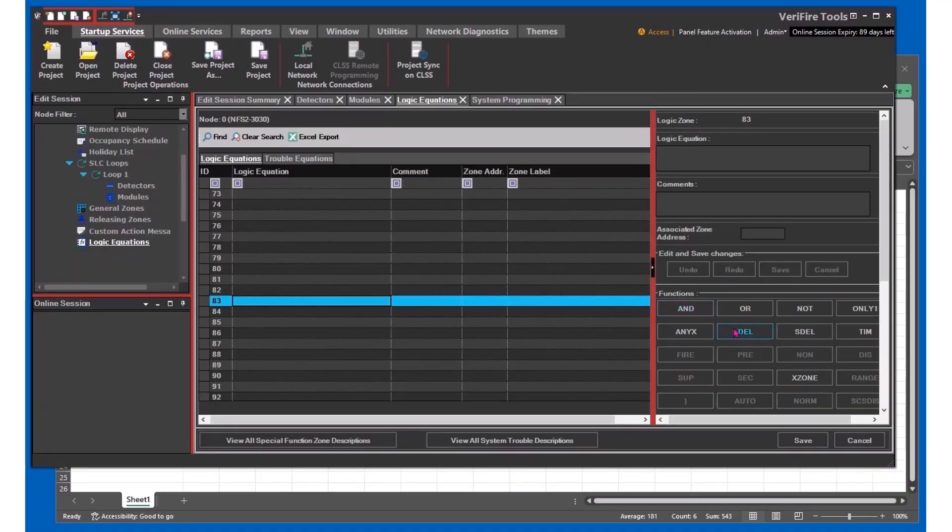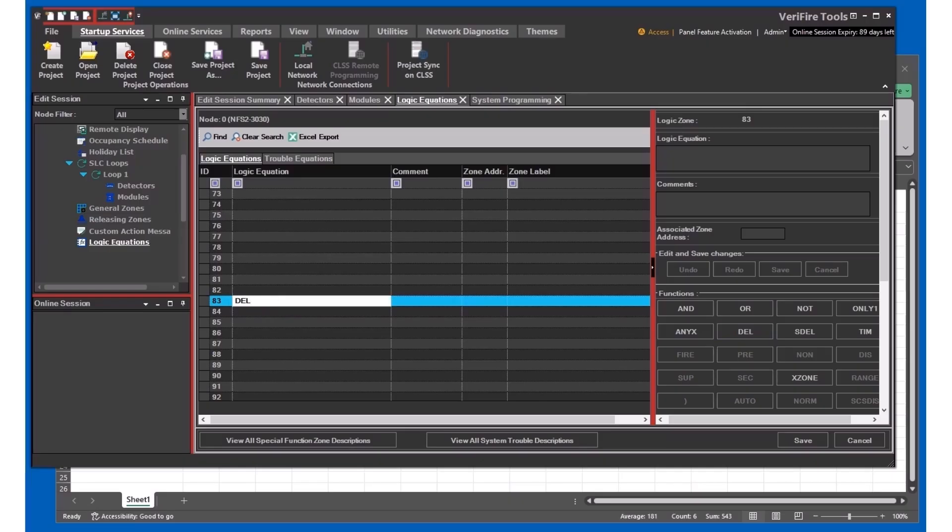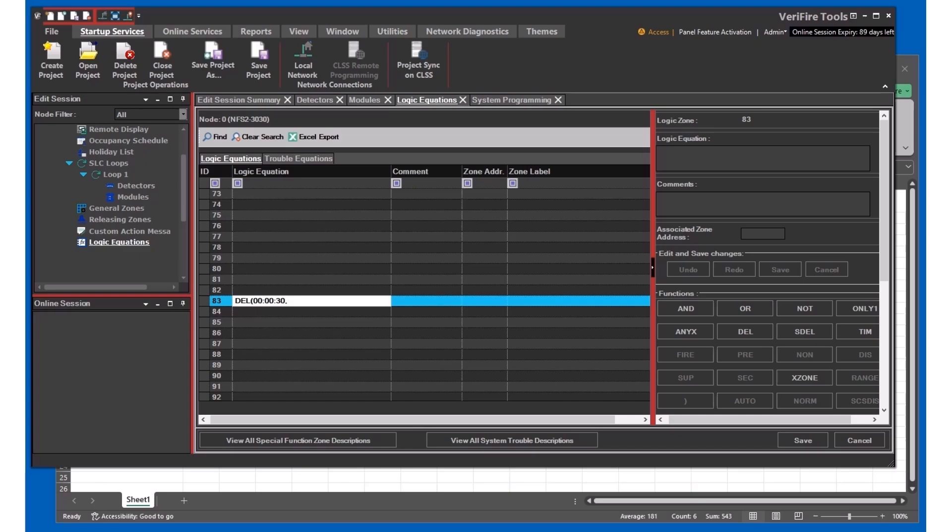Finally, come over to your logic of equations. You can use the builder or you can just type it in manually. So we're going to do a delay DEL for zero hours, zero minutes, and 30 seconds. You'd coordinate this with the elevator contractor. You may need to time the elevator from top to bottom.